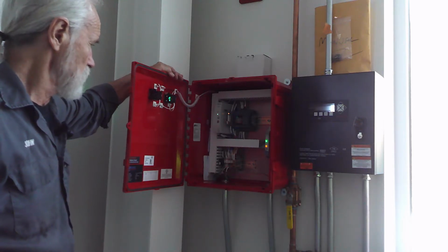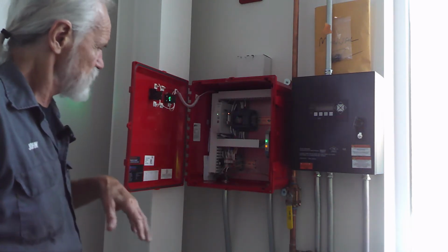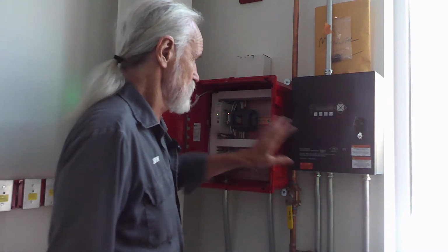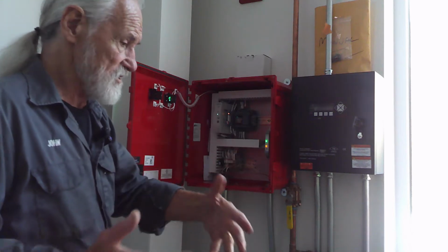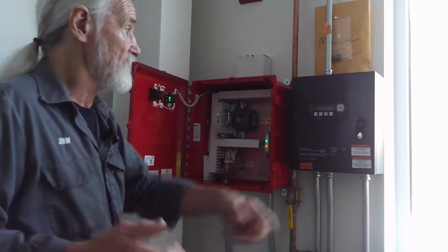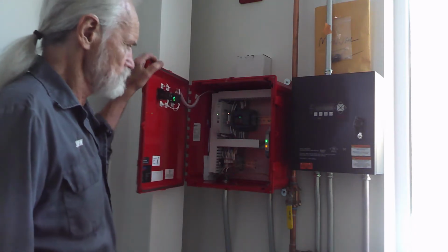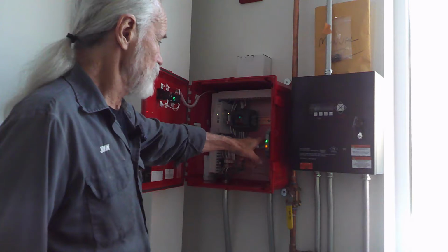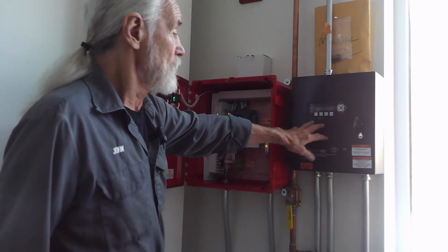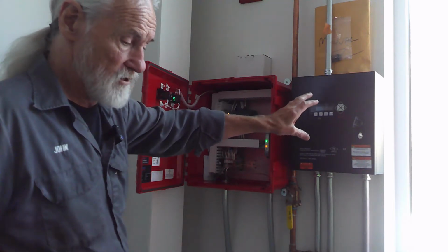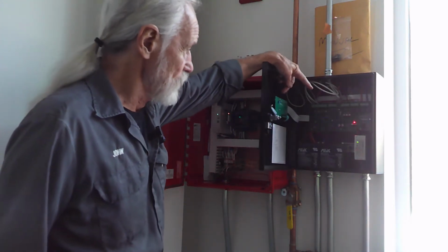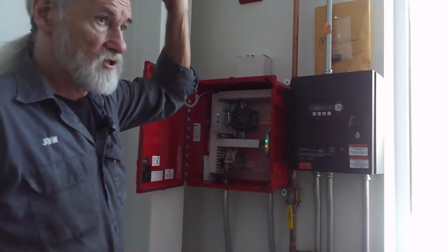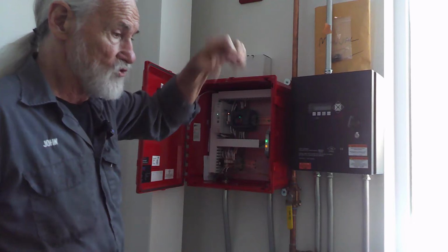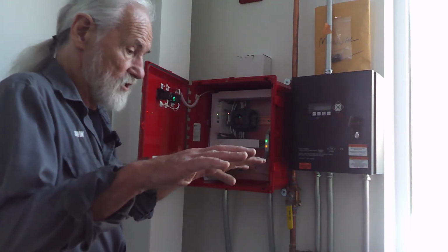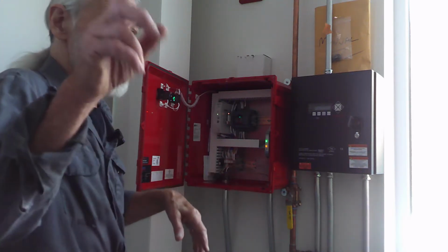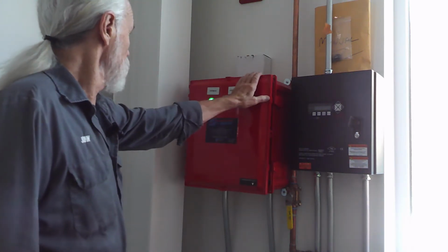Also, which is not your issue really, but these are all dedicated circuits, so that it's not hooked into something else and somebody else decides they want to work on a fan that's hooked in and they shut it off and now they've shut off the fire alarm system. This one has one dedicated circuit just for its power supply, and this one has two: one for the board itself, the controller, and then one for that damper. The damper has a solenoid on it that holds it open. That's high voltage, so it has its own breaker. Okay, let's go and take a look at the unit.